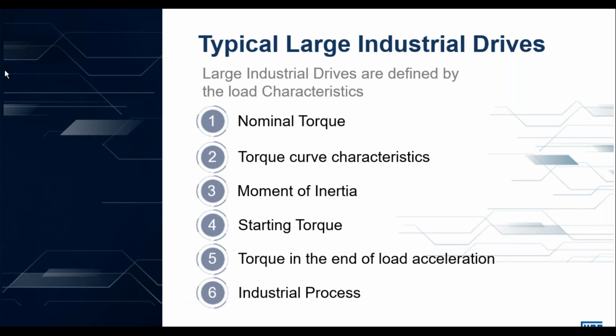Then we need to know the starting torque requirement of the load, and that will determine a lot in terms of the design of the motor and whether we need to apply some special design as opposed to a standard squirrel cage machine. Then number 5, the torque in the end of load acceleration. So when you ramp up a motor, when you get to full speed, in most cases, in most applications, you would have the full load applied from the beginning of the acceleration period right up until the end point when the motor is running at full speed. However, there are some applications where this is not necessarily the case, and we will discuss those in more detail, because there's some fancy footwork that we can do there in terms of some optimized starting techniques.